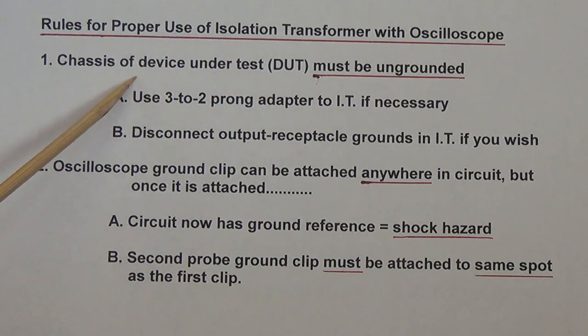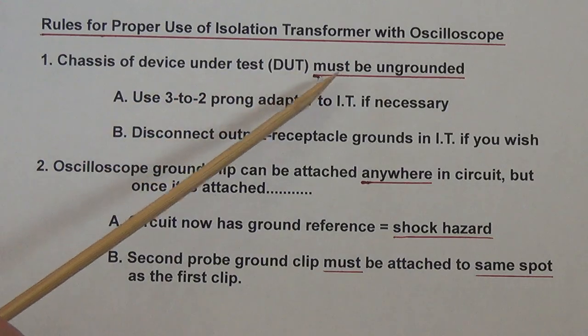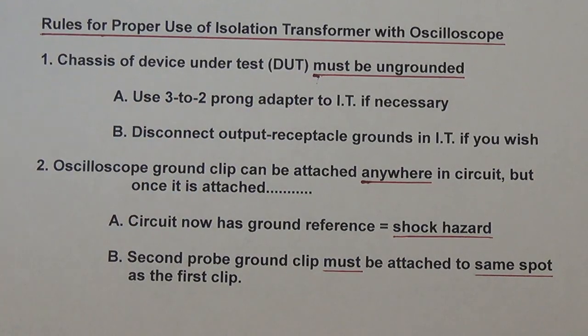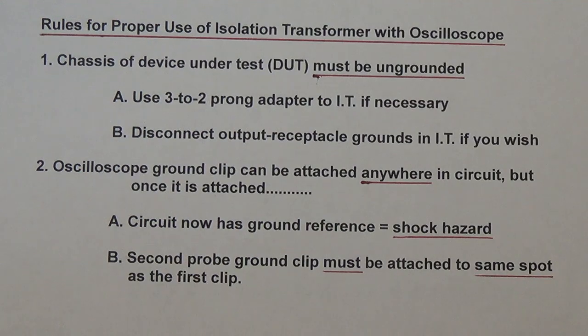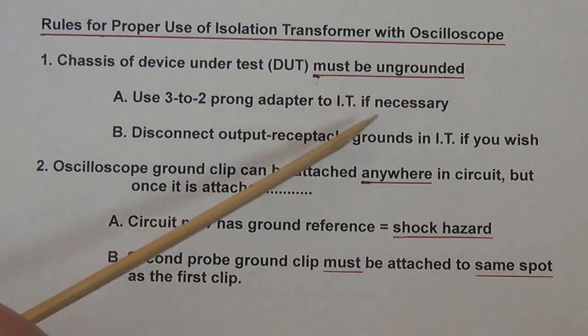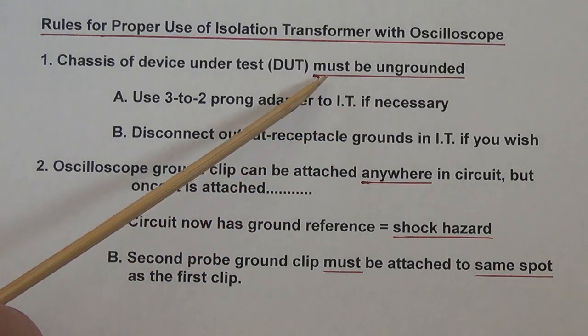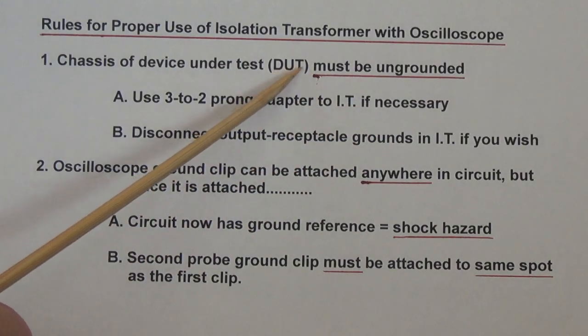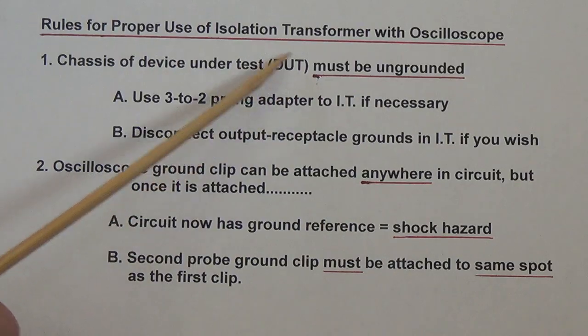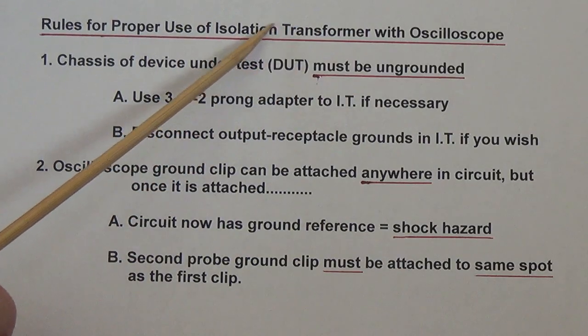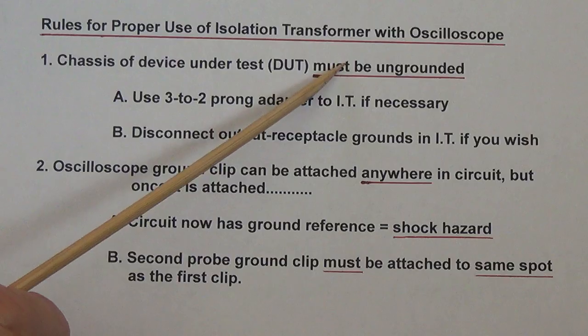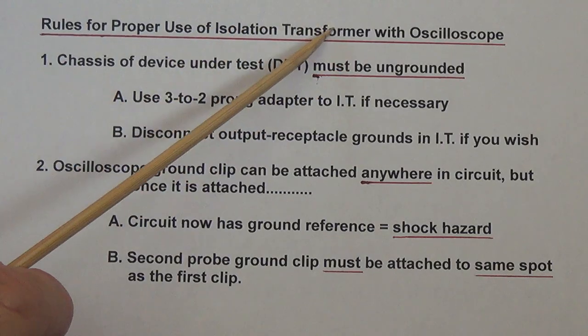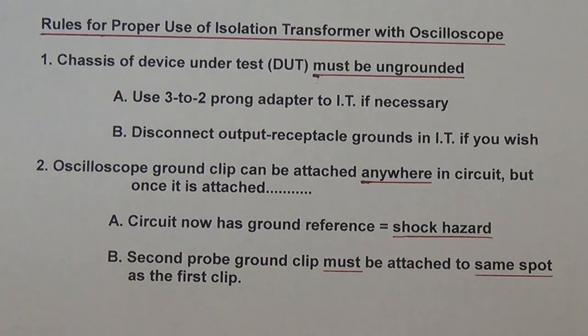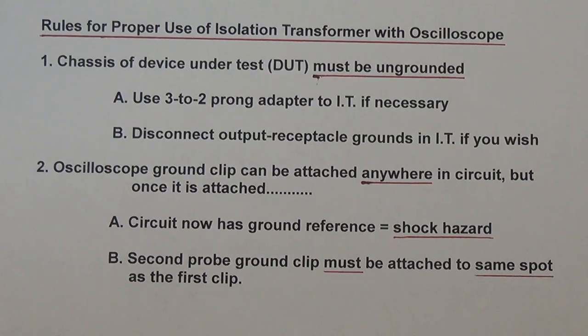Rule number 1, the chassis of the device under test must be ungrounded. If you are one of those individuals who refuses to work on any device that doesn't have a grounded chassis, then that's fine, but you're wasting your time by using an isolation transformer. The minute you ground the chassis, you're losing any benefit that would have been derived from the isolation transformer.